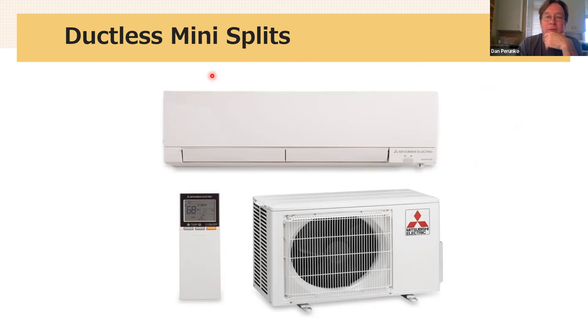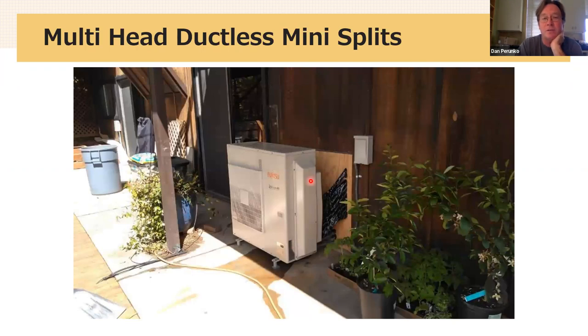There's another thing about this that we'll pick up again later in the talk, which is simply that this is not ducted, right? Which means it's in a space and it conditions the space that it's in very effectively. There are other rooms in the building, typically around the corner, and this machine will do a much worse job conditioning rooms that it can't actually see. The better the building enclosure gets, the less important that distinction is, but it's something to keep in mind, right? This is basically a space conditioner in the sense that it's conditioning the space that it's in, whereas other machines, like a ducted system, could reach into more parts of the house.